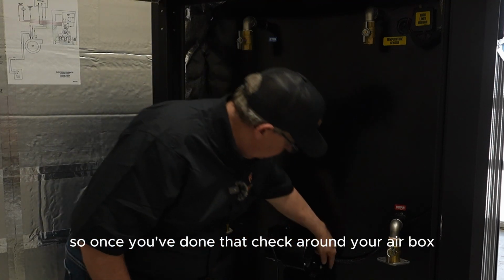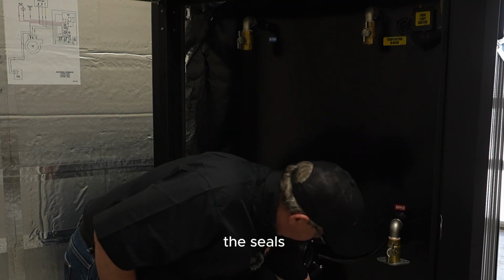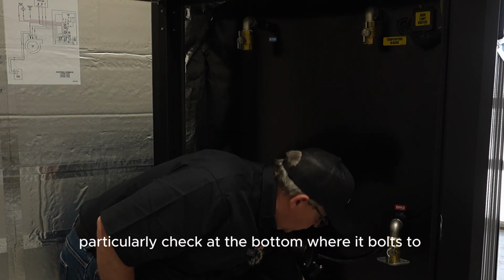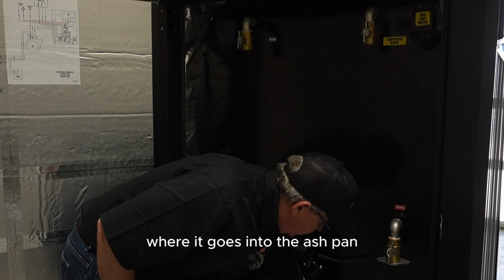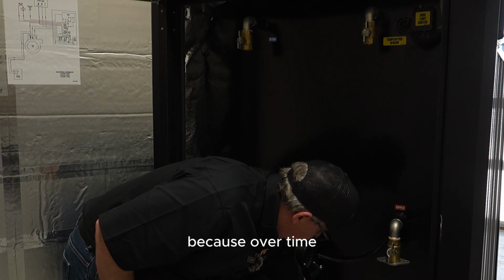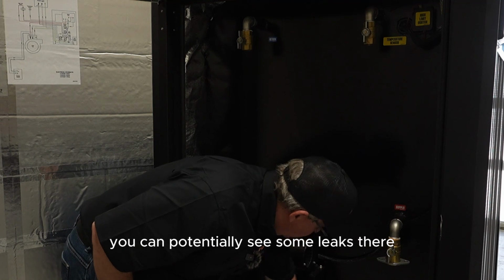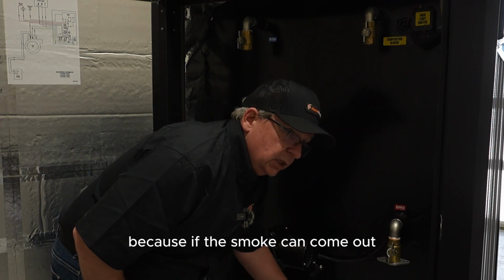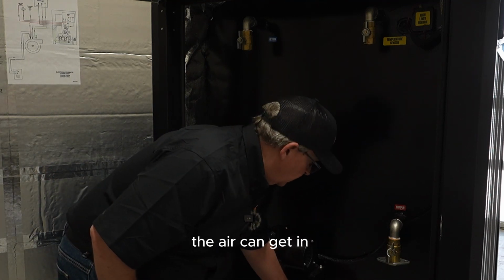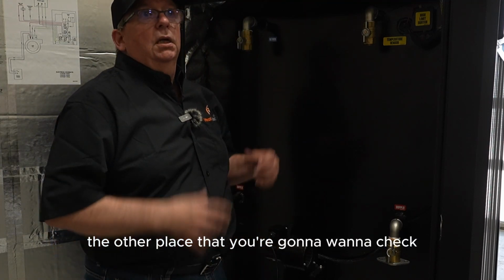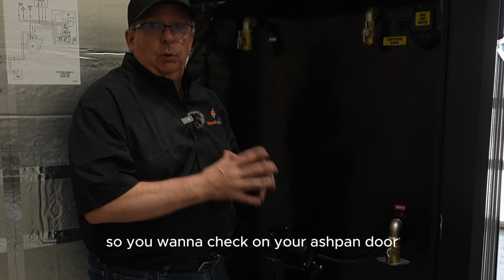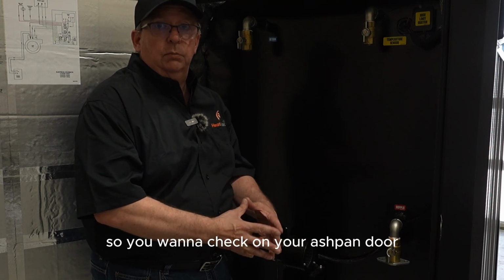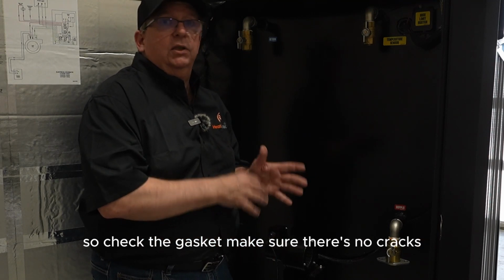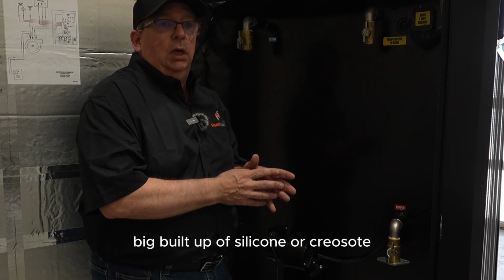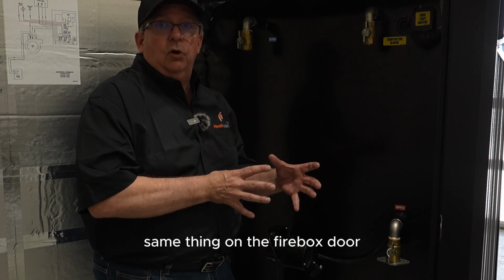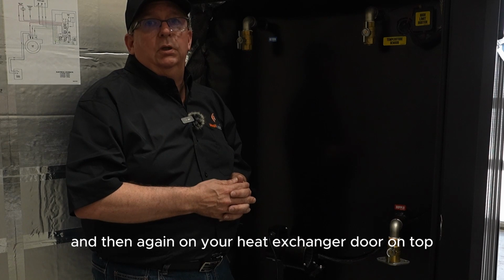Once you've done that, check around your air box, the seals, particularly check at the bottom where it bolts to the bottom of the furnace, where it goes into the ash pan, because over time you can potentially see some leaks there. All it takes is a little puff of smoke, because if the smoke can come out, the air can get in. The other place that you're going to want to check is around all of your door seals. So check your ash pan door, check the gasket, make sure there are no cracks or big buildup of silicone or creosote. Same thing on the firebox door, and then again on your heat exchanger door on top.